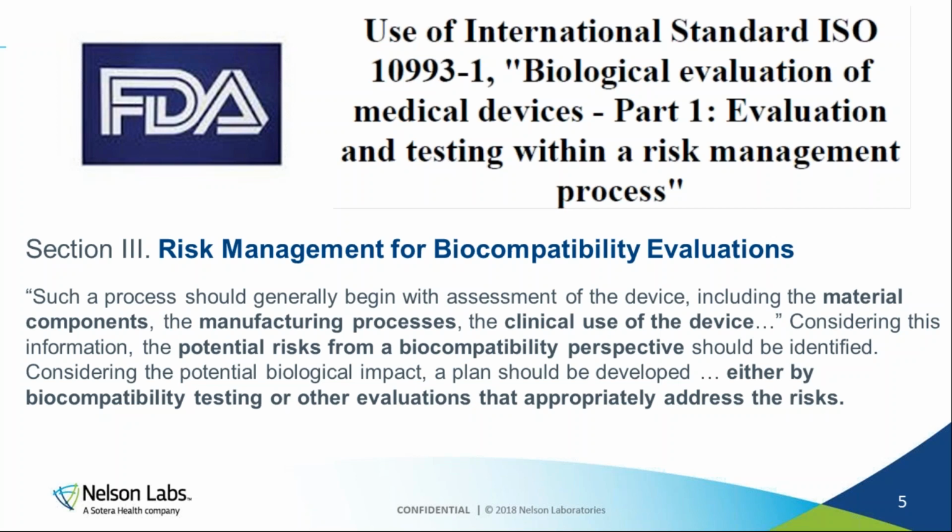Within this section, they've highlighted some components that should be considered in this evaluation, and I have put them in bold on this slide. Specifically, material components, manufacturing processes, the clinical use of the device. These things shall be taken into consideration from a biocompatibility perspective, and then they should be used to determine what next needs to be evaluated, and that can be done by testing or through written risk assessments.